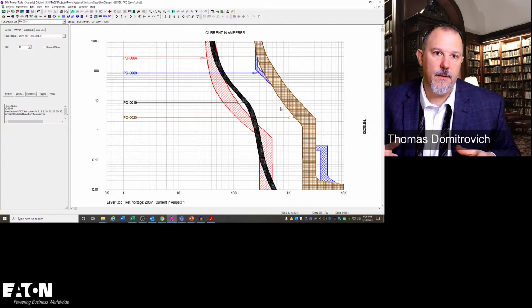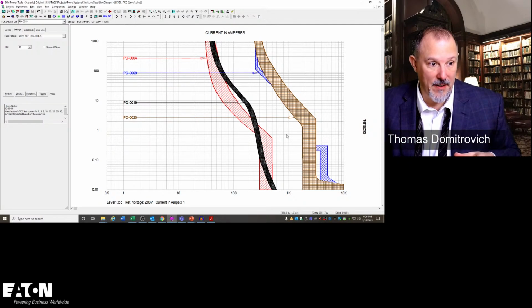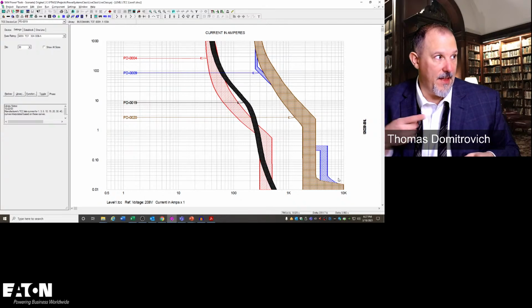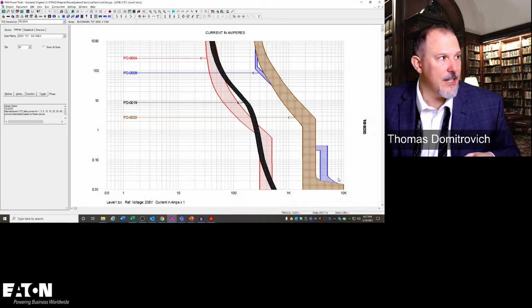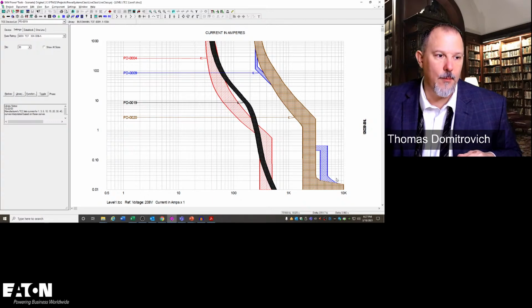I have lowered my incident energy probably as well, because where was my fault current? Way over here in 8,000 amps. Think about that. I'm way into the instantaneous region of that breaker, that 225 amp breaker. I'm way over there on that breaker. So my arcing fault currents, my ground fault current was 8,000 some amps.